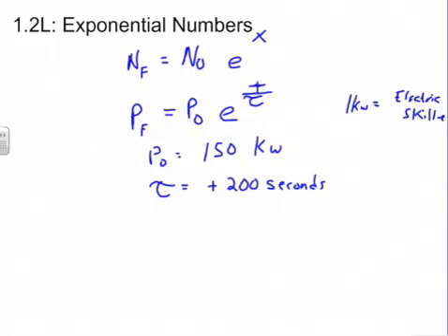Normal values of an up power are somewhere around 100, 120, 150 seconds. 200 is kind of pushing it, but we're going to move this reactor right along. And then let's talk about our time here, and let this reactor increase in power at this plus 200 seconds of reactor period for 15 minutes.